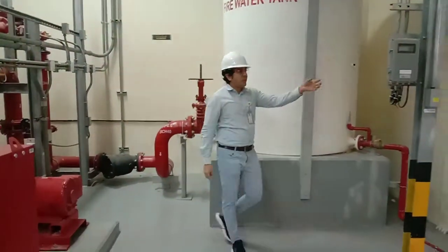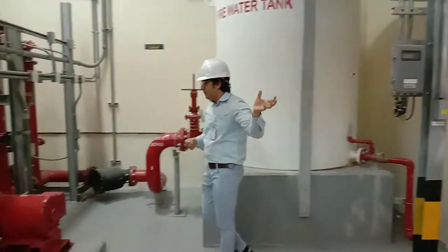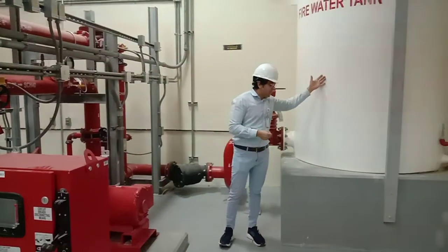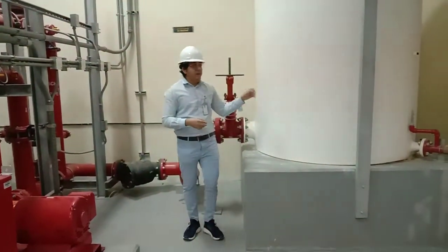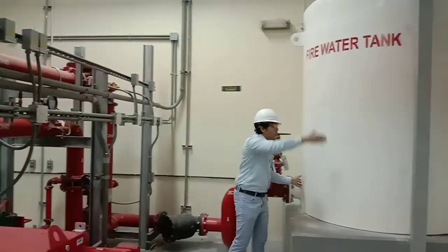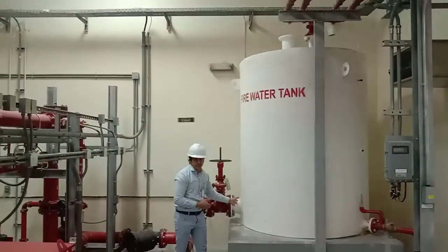With this one, we don't need any kind of pitot tube arrangement or any kind of gauge to measure the pressure at all. It can come inside the suction line, or you can discharge outside also. But keep in mind, the discharge water coming from the pump at full capacity, those lines should be possibly as far a distance from the suction connection.